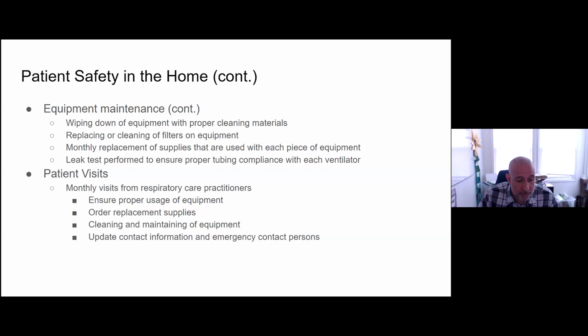With the ventilator, I wasn't quite sure where to sneak this in, so I put it at the back of the equipment maintenance, because every time we change the tubing on our equipment, we will do what they call a leak test, which is to essentially make sure that the tubing compliance is adequate for the ventilator, and it knows exactly what the usability is of the tubing. So we run that every time we change the tubing for the equipment, and that makes it perform at its peak performance.